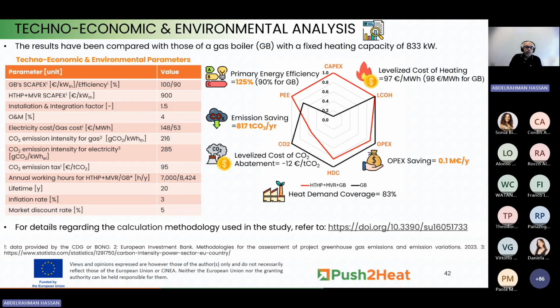Okay? And finally, primary energy efficiency. The heat pump has a significant primary energy efficiency compared with the gas boiler. This means that the heat pump in this scenario can produce an amount of heat equal to almost 1.3 times the primary energy consumption. Okay. For more details about the calculation methodology used in this study, you can refer to this paper, which was published recently by the partners in Work Package 5 in the Push2Heat project.